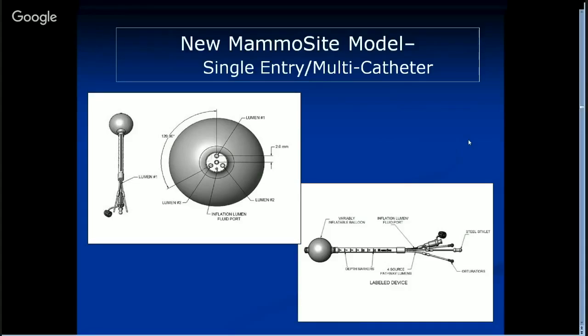You can fill in liquid and shoot out the air. That's a good design. But you need to know that the peripheral lumen is preferably located only 2 millimeters away from the central line, which gives you not that much dose modulation.